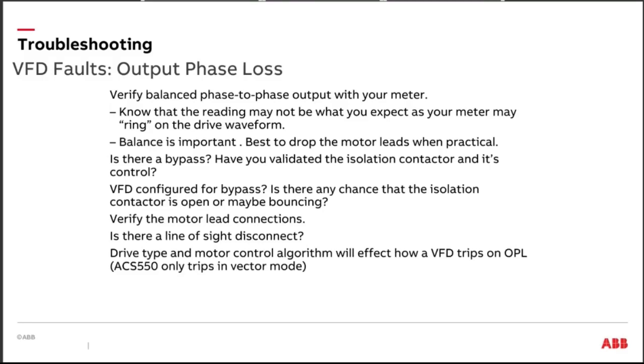That's true. I've had this at an aluminum plant, back when the Baldor drives were still here, nine years ago. We had an issue. The user would put a disconnect at the motor, and the electrician would go out, open the disconnect and close the disconnect at the motor, and it would trip the drive on instantaneous overcurrent. Well, today's drives, the IGBTs operate so fast that if you do close that disconnect, we're not really worried a lot about destroying the IGBTs. It's not a good idea. It's a bad work habit as far as I'm concerned. But the drive is going to shut down really, really fast. Okay, but just the same, it's a bad idea.